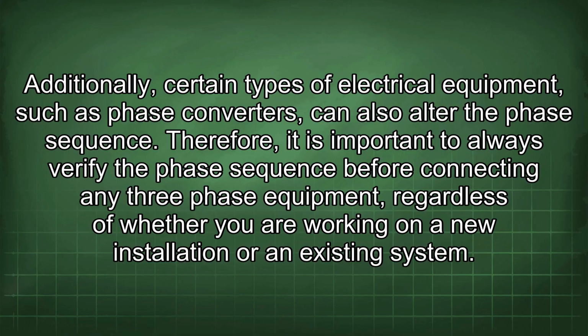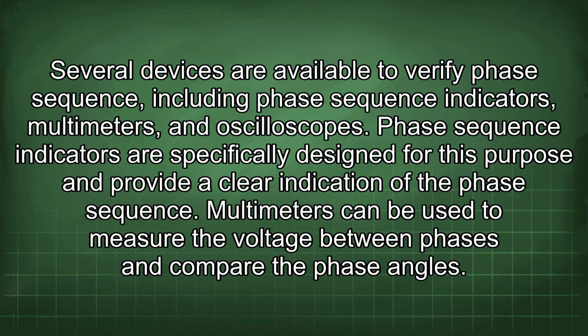Therefore, it is important to always verify the phase sequence before connecting any three-phase equipment, regardless of whether you are working on a new installation or an existing system. Several devices are available to verify phase sequence, including phase sequence indicators, multimeters, and oscilloscopes.